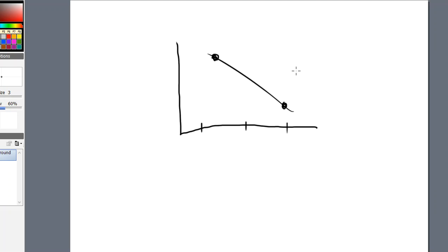And to do that, we will at least use 3 buffers, so that way that third buffer can give us a better story. That third buffer can ensure that these 2 buffers make a straight line, and that one is not weird like the other one is. So for instance, if we did a 3-point buffer, and we did a pH of 4, and let's say that we did a pH of 7 and a pH of 10.